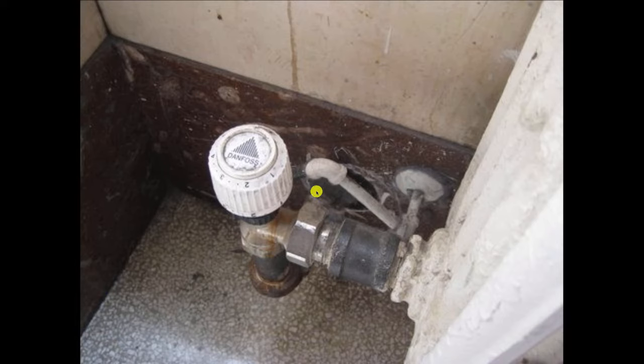And in this case, it gets replaced with a thermostatic radiator valve. And this is a non-electric valve. This one's made by Danfoss. It's a normally open spring-loaded valve. And on the top of it snaps this temperature-sensitive head. Now, it's not sensing the steam, it's sensing the temperature of the air in the room. So as the air warms up, this is very sensitive. And the stuff on the inside, it could be a liquid or it could be a wax, will expand and push down on the normally open spring-loaded valve to lessen the amount of steam that goes into the radiator.